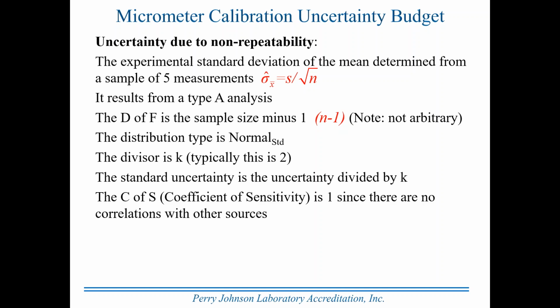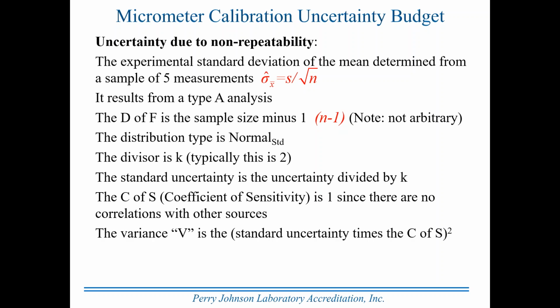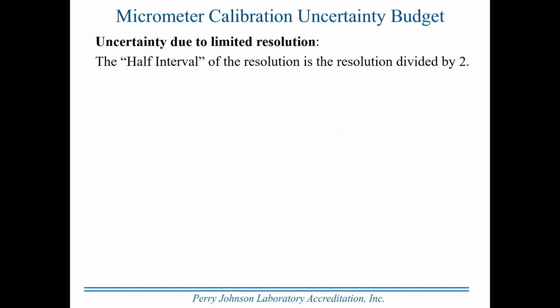Again, there are no correlations, so the coefficient of sensitivity is 1. And the variance in all cases is going to be the standard uncertainty times the coefficient of sensitivity, and that product raised to the 2nd power. Uncertainty due to limited resolution.